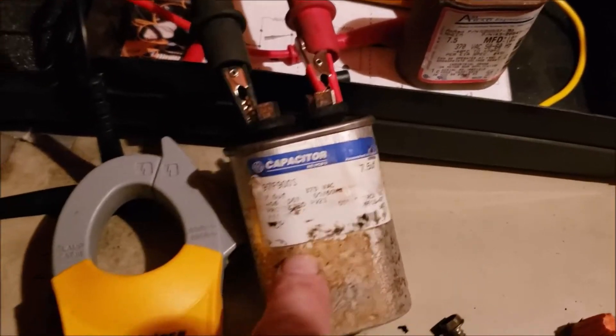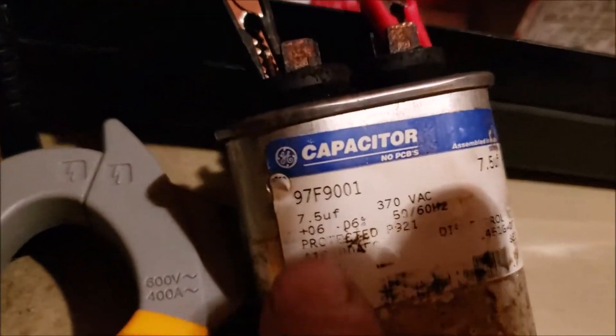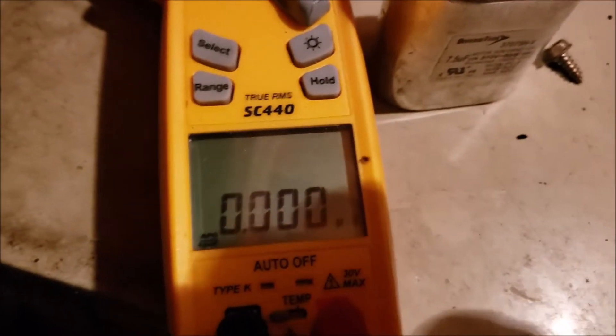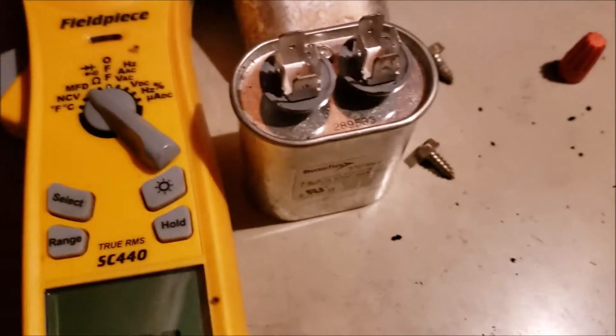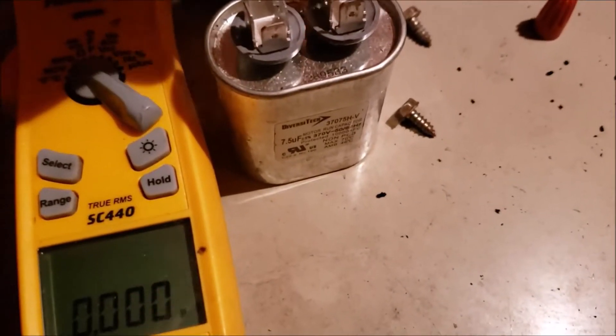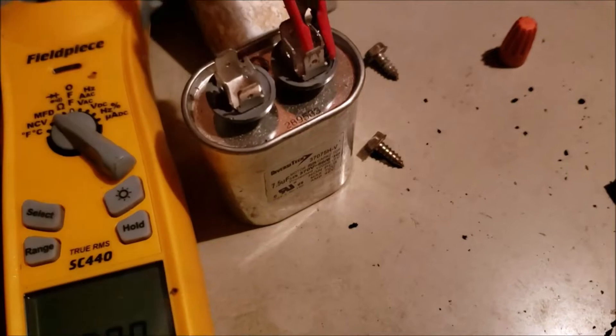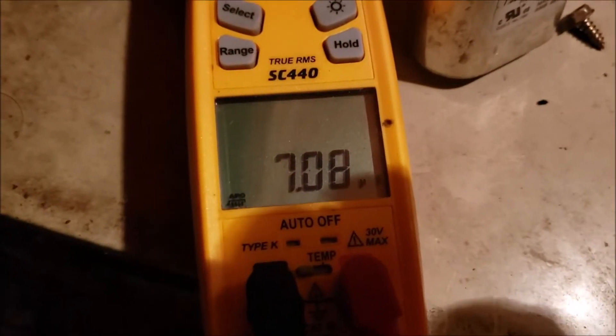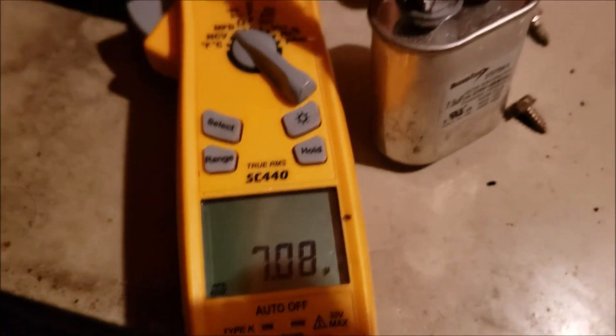Here's the original capacitor I pulled out — you can see it should be 7.5 UF, and when I put my meter on it we got nothing. So I got another one here to show you the difference. I connected it with one hand, and now we got 7.08 UF. Alright, so we're in good shape.